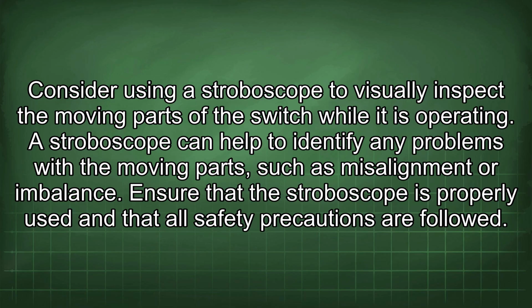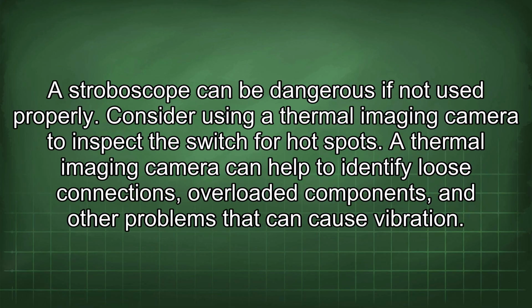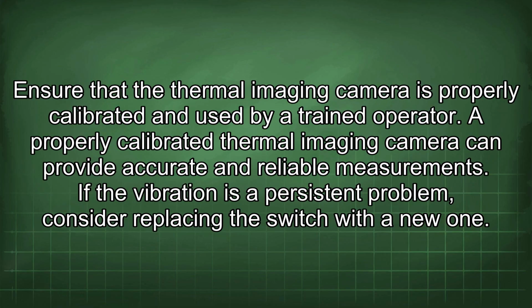Consider using a stroboscope to visually inspect the moving parts of the switch while it is operating. A stroboscope can help to identify any problems with the moving parts, such as misalignment or imbalance. Ensure that the stroboscope is properly used and that all safety precautions are followed. A stroboscope can be dangerous if not used properly. Consider using a thermal imaging camera to inspect the switch for hot spots. A thermal imaging camera can help to identify loose connections, overloaded components, and other problems that can cause vibration. Ensure that the thermal imaging camera is properly calibrated and used by a trained operator. A properly calibrated thermal imaging camera can provide accurate and reliable measurements.